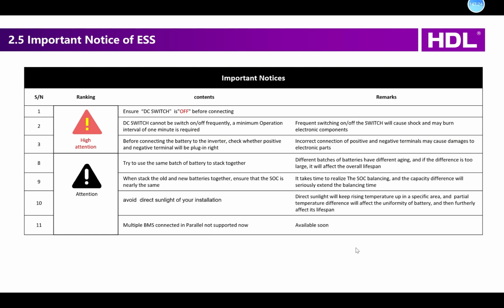And also you need to avoid direct sunlight against the battery, because it will keep raising the temperature of this specific area of the battery. So it will have partial temperature differences, and this will affect the consistency or uniformity of the battery, and affect its lifespan. And right now, multiple BMS connected in parallel is not supported, and will be available soon.